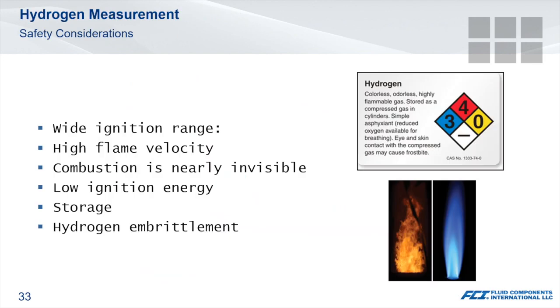Several considerations come into play for the safe handling of hydrogen. Hydrogen has an ignition range of 4% to 74% in the presence of air. Its flame velocity is 5.6 feet per second, which is 4.25 times faster than natural gas. Since its combustion is nearly invisible, open flames are not noticeable and can lead to accidental burns if not careful. Hydrogen gas has a low ignition energy compared to natural gas.